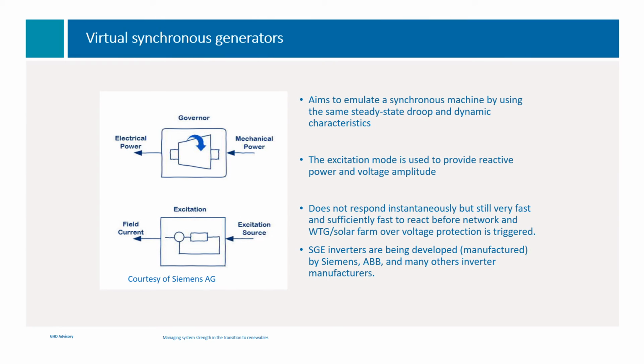A number of inverter manufacturers have recognized the issue with control systems on traditional inverters for solar PV and wind turbine generators, and have developed what Siemens calls a synchronous generator emulating inverter, or SGE. It aims to emulate a synchronous machine by using the same steady-state droop and dynamic characteristics. The excitation mode is used to provide reactive power and voltage amplitude. Whilst it does not respond instantaneously to a network disturbance, it does respond sufficiently fast to react before network and wind turbine generator or solar farm overvoltage protection is triggered. Siemens and ABB and many other inverter manufacturers are now looking to improve the development of inverters to be able to provide system strength, and indeed this ABB and Siemens inverter is able to provide up to 3 per unit overcurrent in response to a network disturbance.